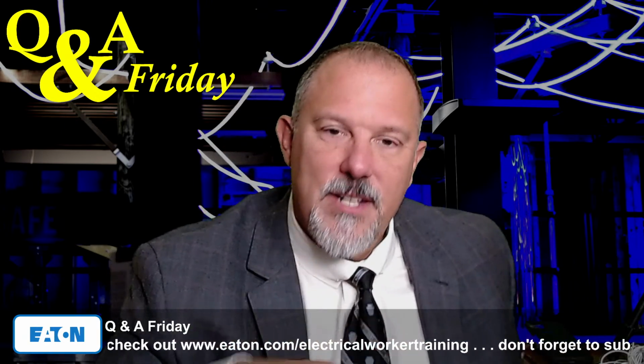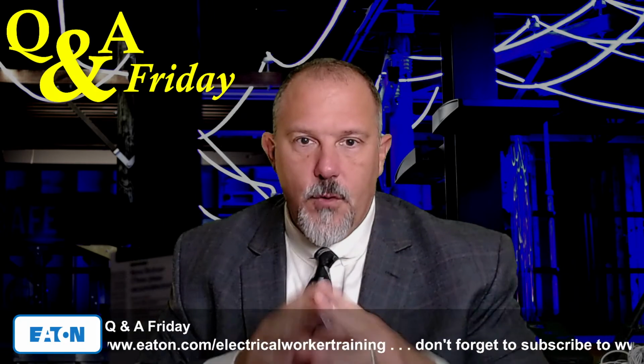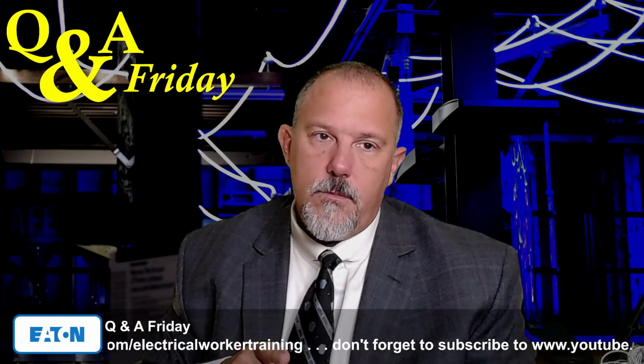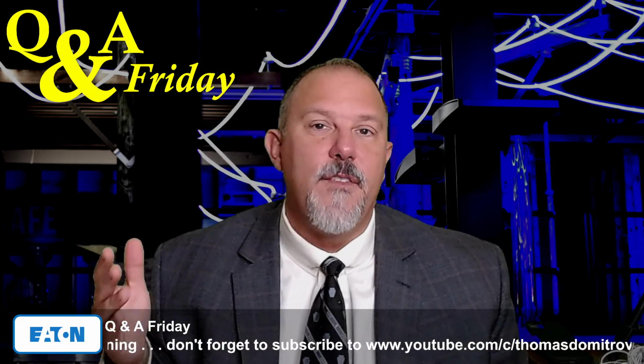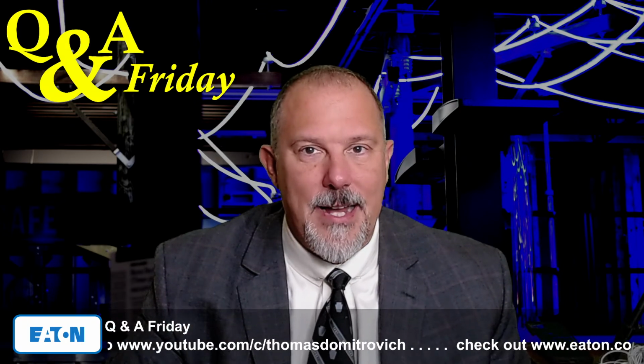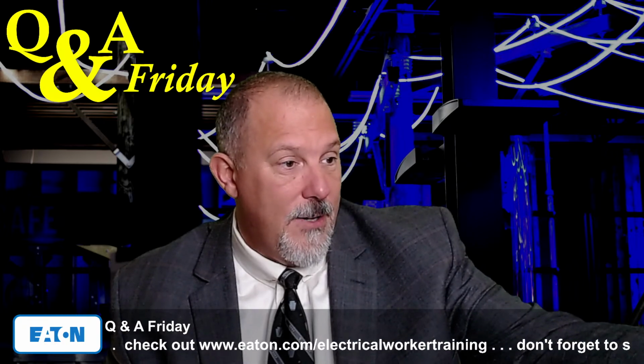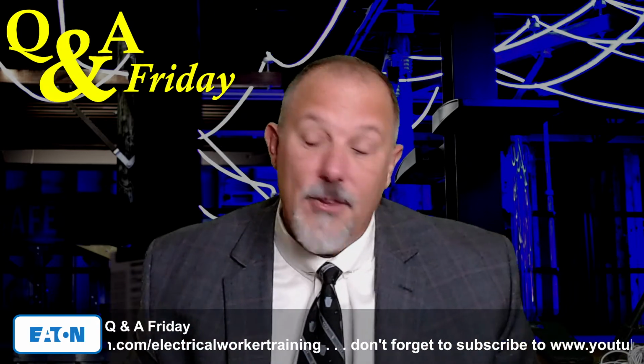So here's my thought process. Remember, on these transformers, if you're doing your full load amp calculation, if you calculate the secondary, you can get the primary simply by reflecting the secondary to primary based upon the turns ratio. So I can take my secondary full load amps, multiply it by the secondary line-to-line voltage divided by the primary line-to-line voltage, and that'll give me my primary full load amps.